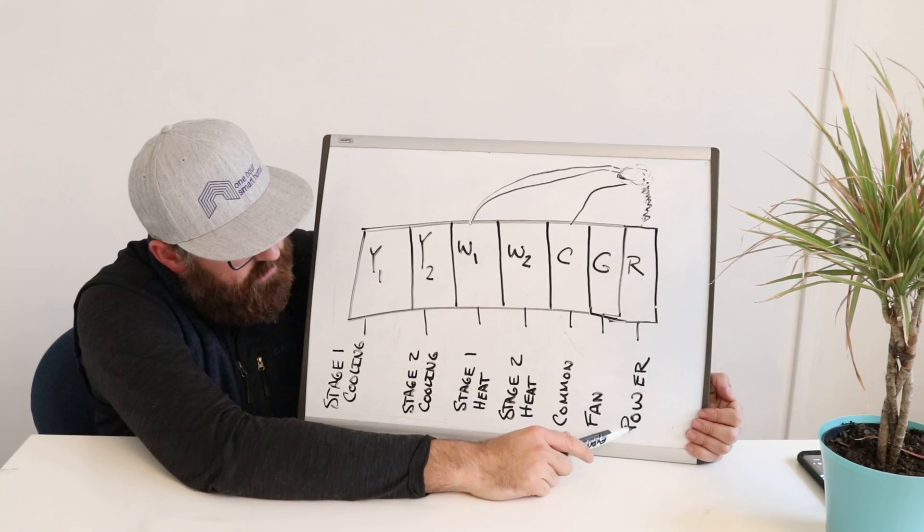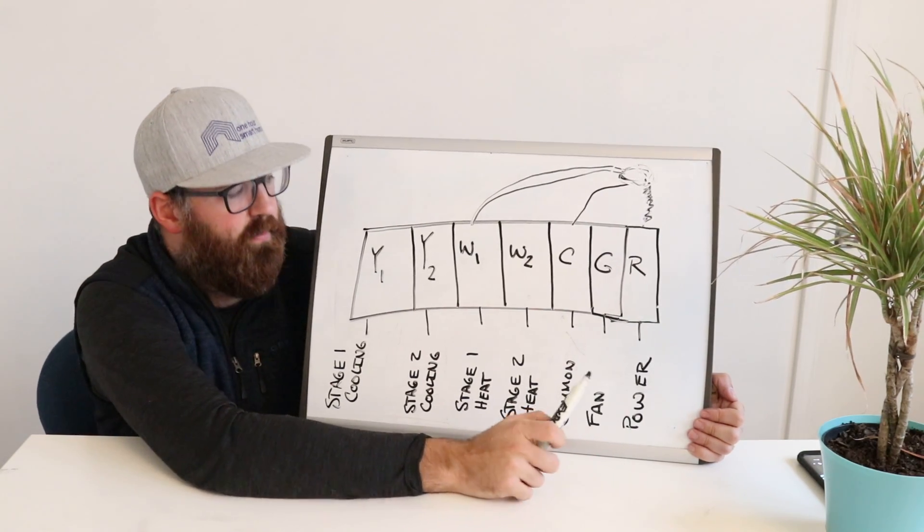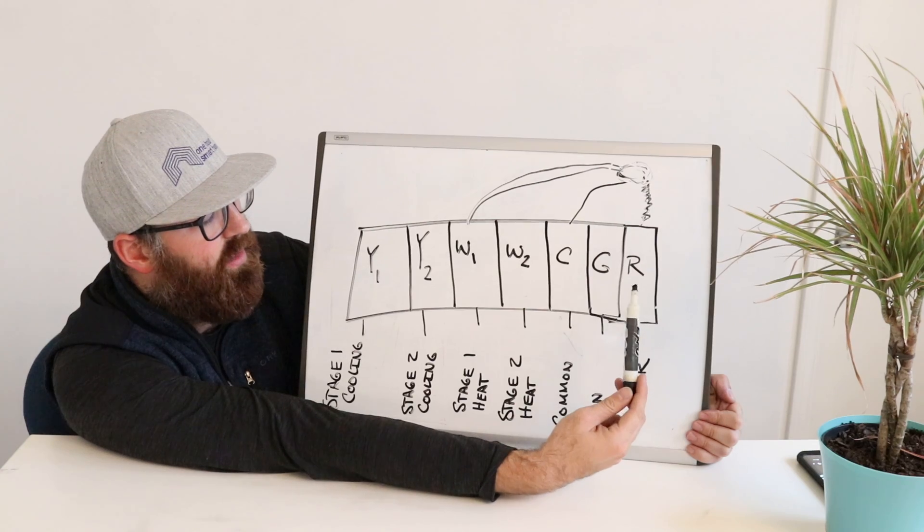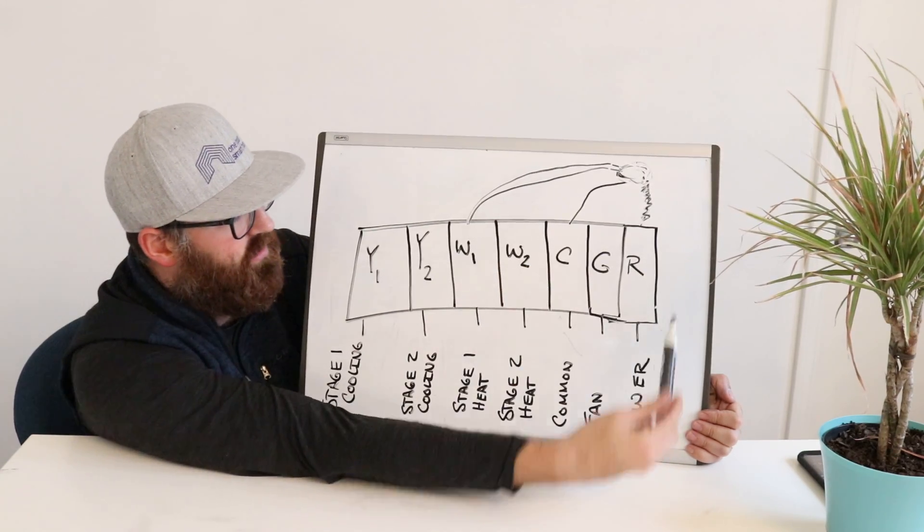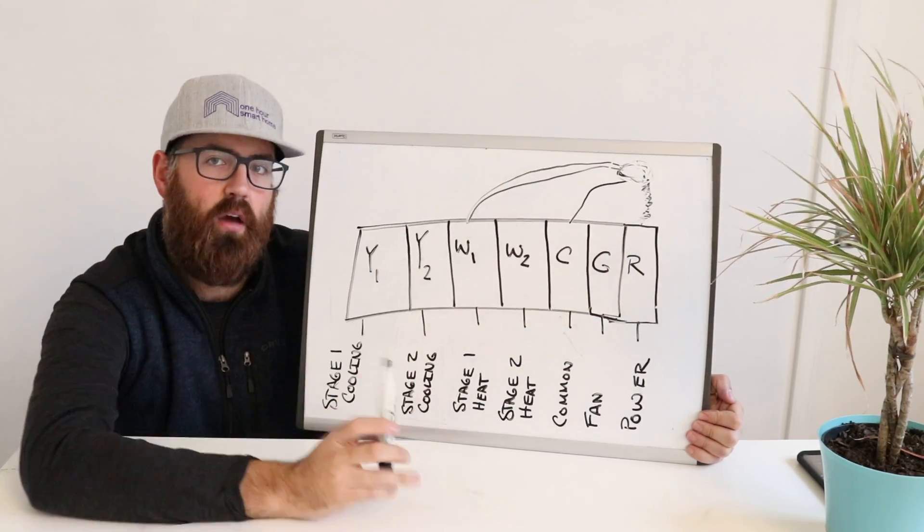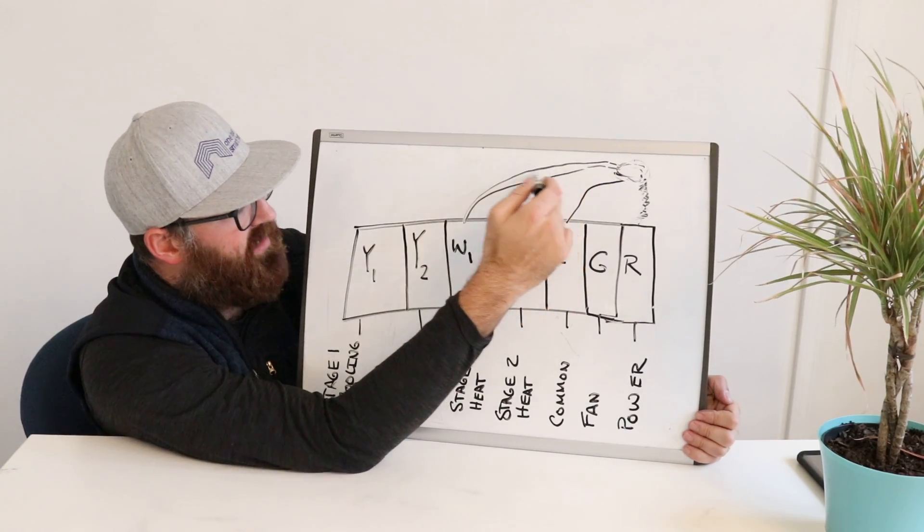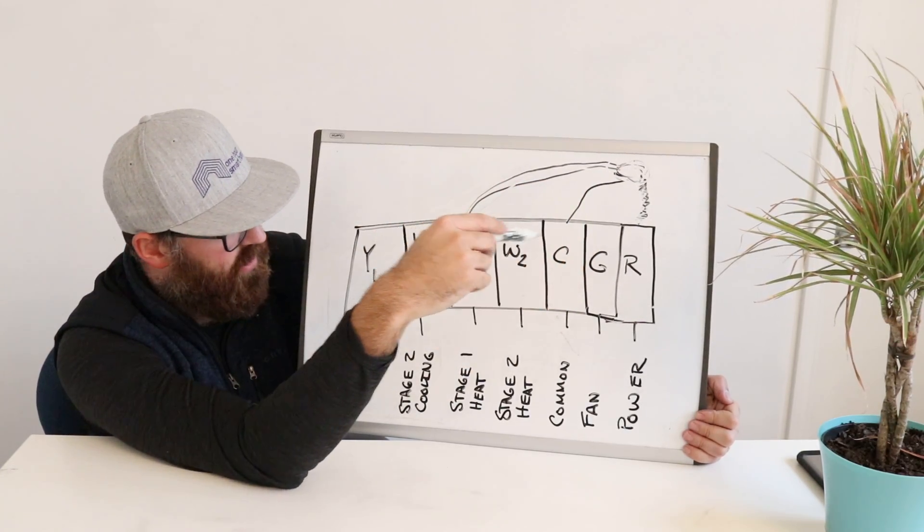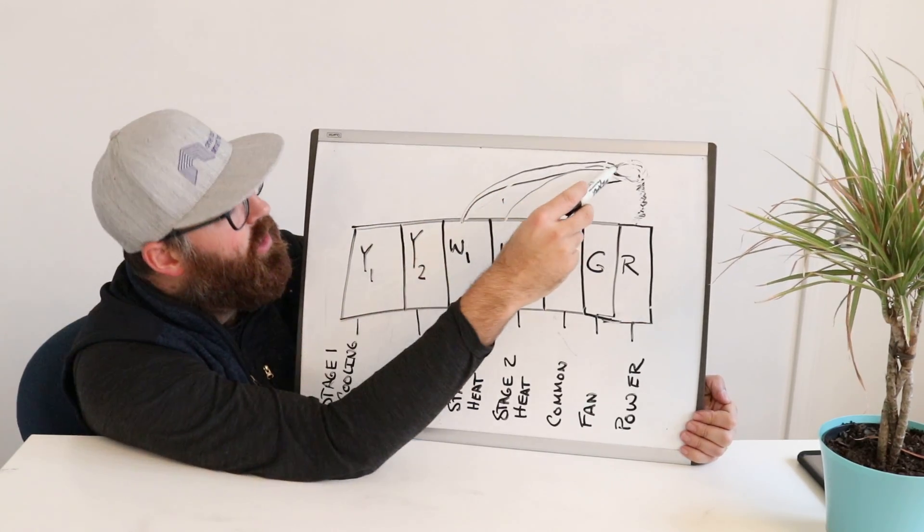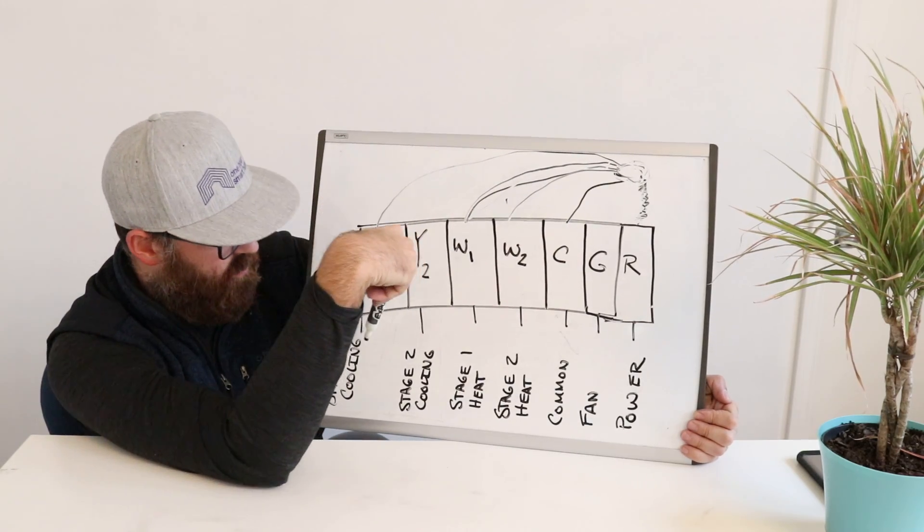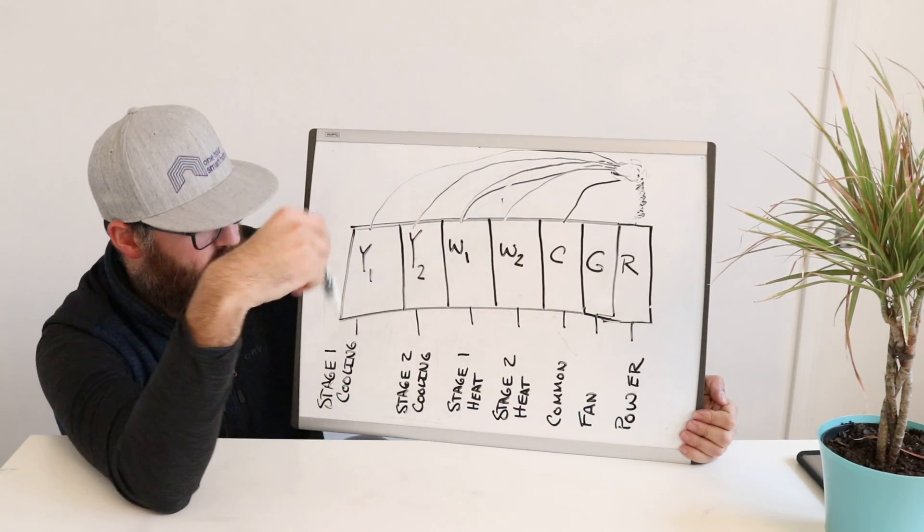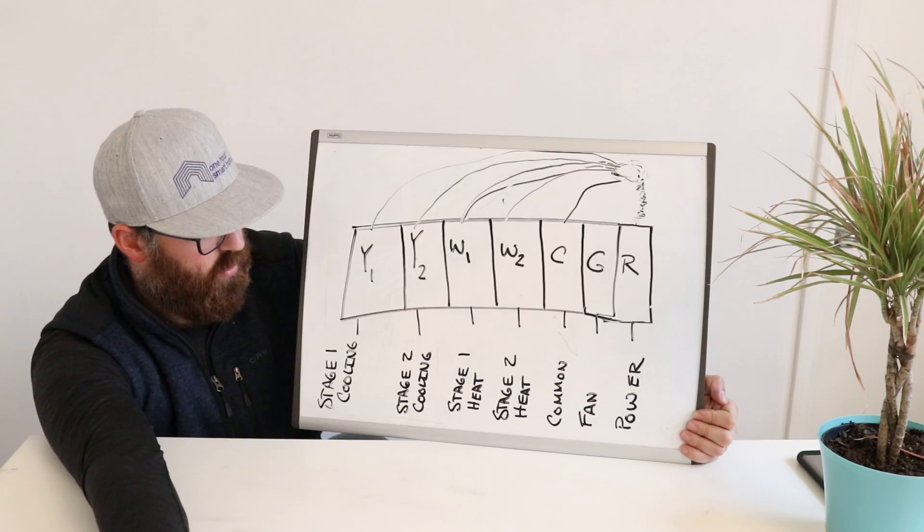Now last but not least, let's not forget the R wire, the power wire. This R terminal and wire inside the furnace is providing the power that is used to make any of these other connections. So power goes out from the R wire up to your thermostat, and depending on what you have your thermostat set to, will either then go back down to the W1 wire for stage one heat. If you want more heat, it'll go down to the W2 wire for stage two heat. If you want cooling, that power will go down to the Y1 wire and it will give you cooling. And if you want lots of cooling, it'll go down to the Y2 wire and give you the most cooling possible.